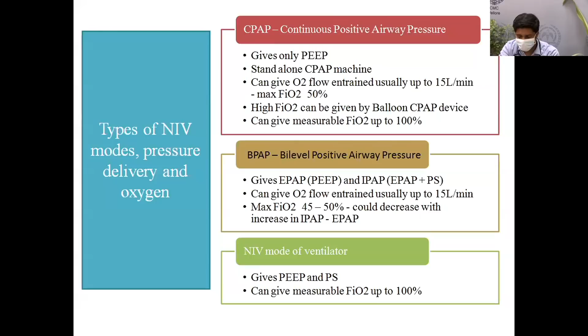In a BiPAP machine, it has both the EPAP and the IPAP. EPAP behaves as a PEEP, and your IPAP minus the EPAP, the inspiratory pressure, will behave as the pressure support. O2 flow can be adjusted up to 15 liters here, and the maximum FiO2 achieved here can be only 45 to 50%. Another mode of ventilation is the NIV mode of ventilator, which gives both the PEEP and the pressure support, and we can increase the FiO2 up to 100% in NIV mode of ventilator. So these are the different oxygen delivery devices available in the level 1 and level 2 wards.